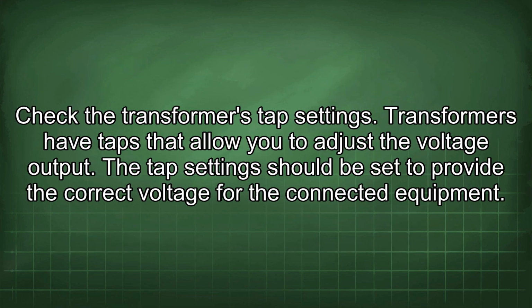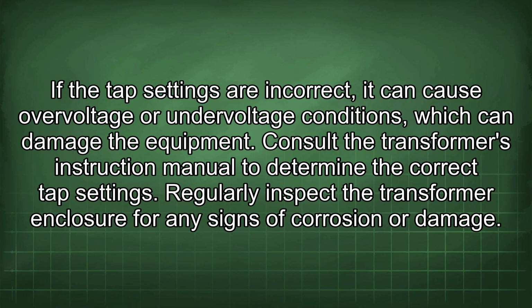Check the transformer's tap settings. Transformers have taps that allow you to adjust the voltage output. The tap settings should be set to provide the correct voltage for the connected equipment. If the tap settings are incorrect, it can cause overvoltage or undervoltage conditions, which can damage the equipment. Consult the transformer's instruction manual to determine the correct tap settings.